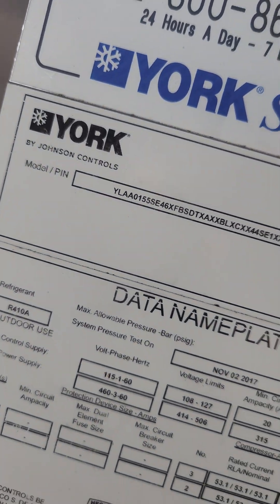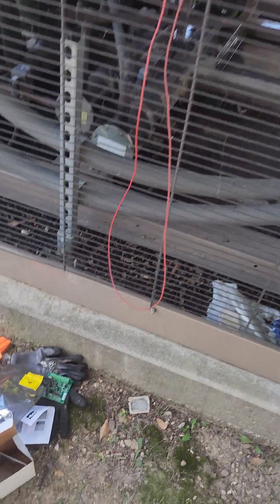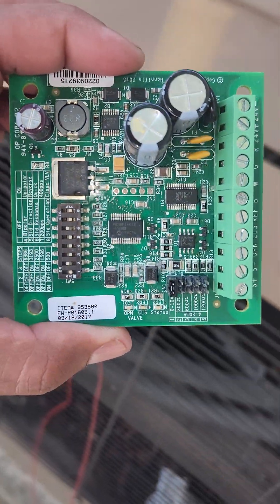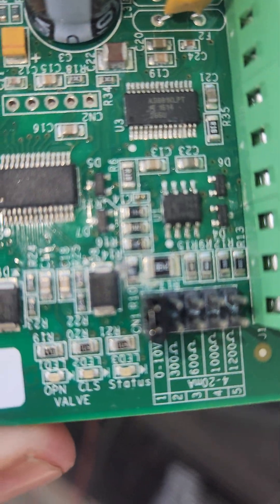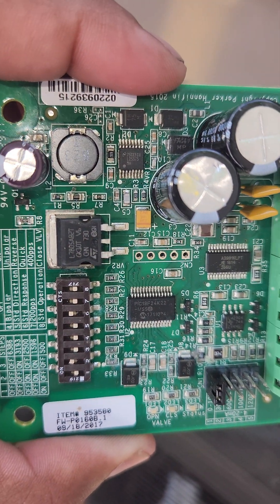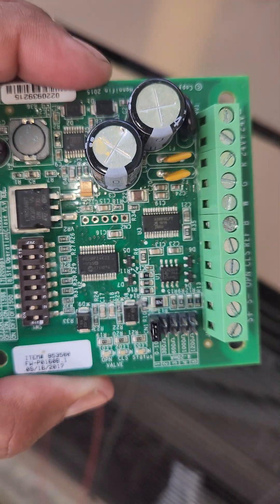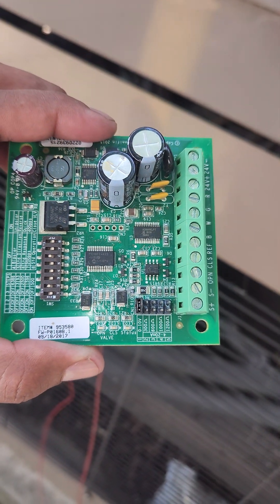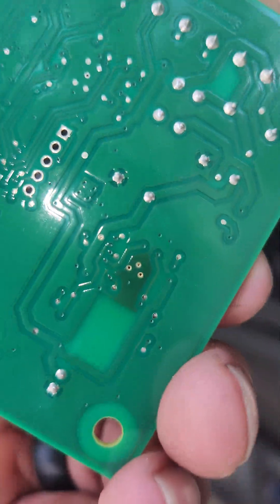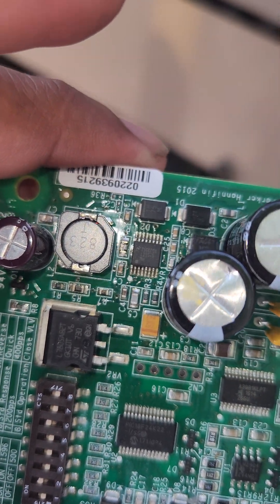It's a York YLAA — an old one right here. It got all wet, you can see it right there, and it wouldn't operate anymore. It looks like it burnt a little bit — you see that? There's the COM chip, the EPROM chip right there.